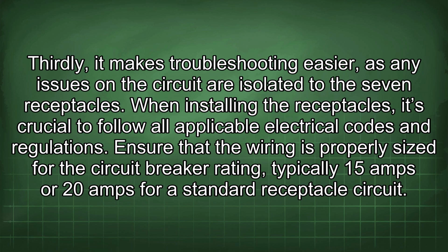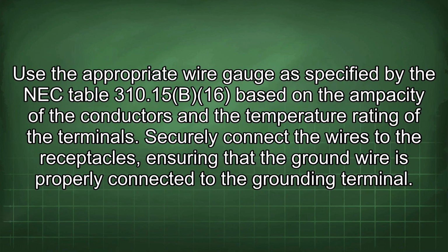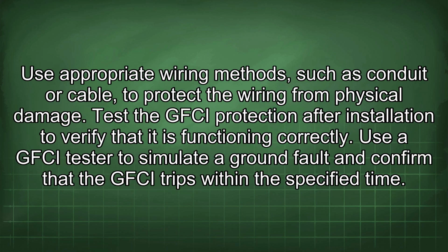When installing the receptacles, it's crucial to follow all applicable electrical codes and regulations. Ensure that the wiring is properly sized for the circuit breaker rating, typically 15 amps or 20 amps for a standard receptacle circuit. Use the appropriate wire gauge as specified by NEC Table 310.15(B)(16), based on the ampacity of the conductors and the temperature rating of the terminals. Securely connect the wires to the receptacles, ensuring that the ground wire is properly connected to the grounding terminal. Use appropriate wiring methods, such as conduit or cable, to protect the wiring from physical damage.